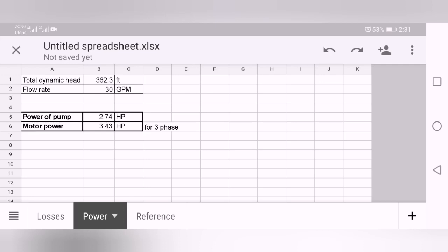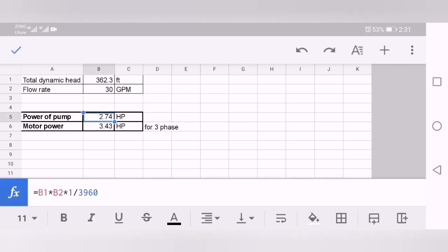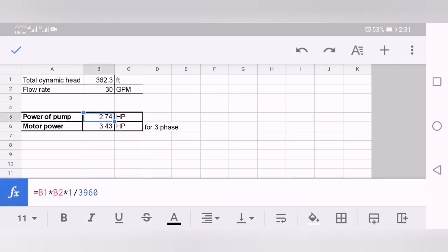What is the equation to solve this? The equation is simple. Here, just multiply the total dynamic head with the flow rate. These units must be in U.S. customary units, that is gallons per minute and feet. B1 is your total dynamic head multiplied by B2, which is your flow rate, and multiply by 1.